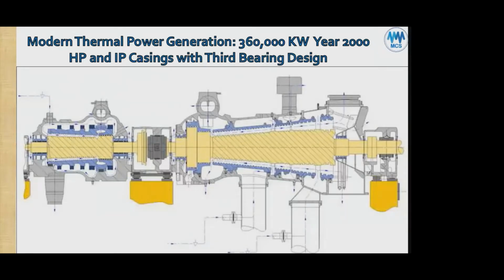Nowadays in modern turbines, obviously, anytime you're above something like 60 or 70 megawatt, the couplings will be solid and no more flexible. Solid hubs, solid coupling hubs. However, the problems of the past, which were heat-induced vibration problems, heat-induced rubbing problems, rotordynamic problems, manufacturing deficiencies, haven't changed. We've been in steam turbines for 120 years at least, and the same evils are still hurting a modern steam turbine. However, bearings are much improved, thank God. That helps a lot in providing damping to those vibrations. Balancing of rotors is far improved from the old days. So we have modern tools that help us. Number three modern tool is vibration analysis, high-tech instruments and high-tech vibration analysis. Knowledge is amazing.